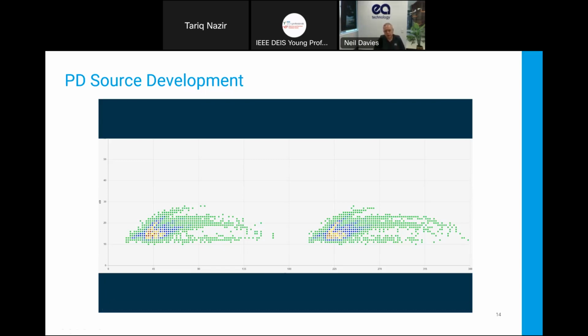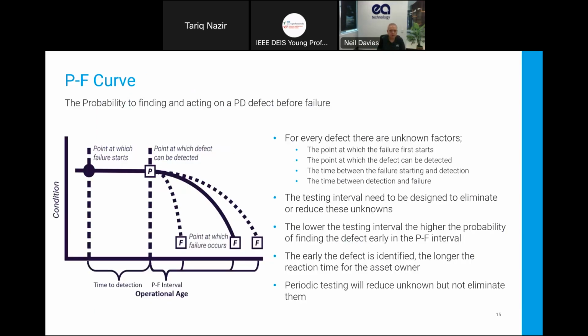So the benefit of having monitoring on there, of course, is that we can see when a defect starts and how it progresses, whereas the spot check won't do that. So we're going to talk about the probability of finding and acting on the defect before failure. Every defect has a lot of unknown factors: the point at which failure first starts, or the discharge defect starts, the point at which it can be detected, and then that time, of course.